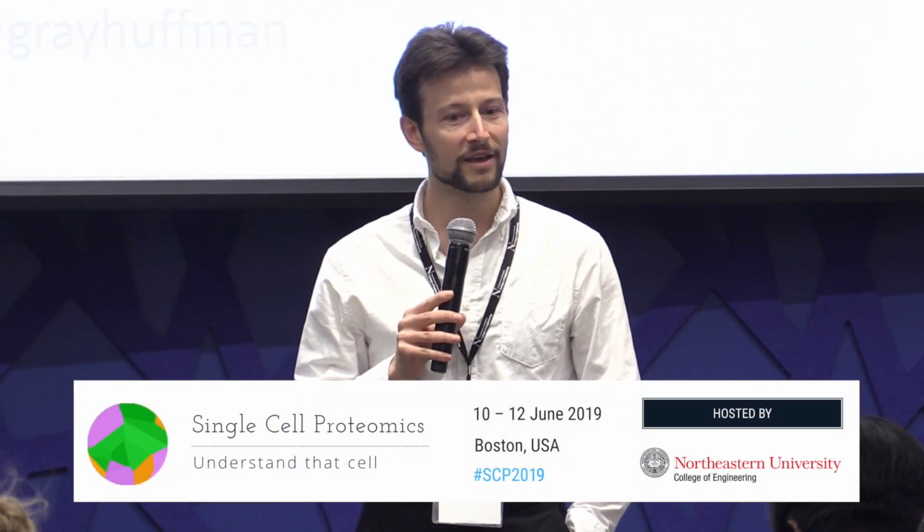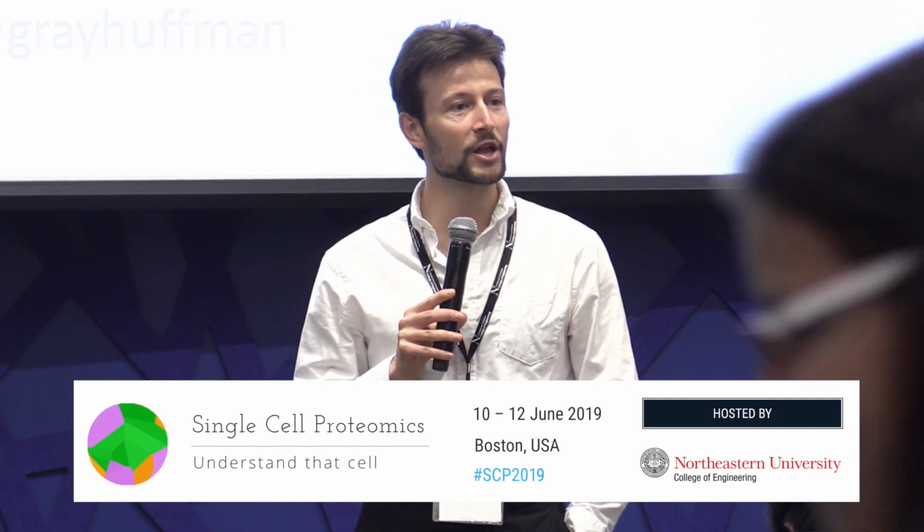So Gray is about to share with you what we have learned the hard way by doing something over and over again, meaning optimizing our instrument parameters and diagnosing what went wrong. Because at the beginning when we started, most of the time things went wrong. We did not have pure spectra. We had very dirty spectra. We did not have high identification rates. We did not have the expected intensities in the various labeled samples.